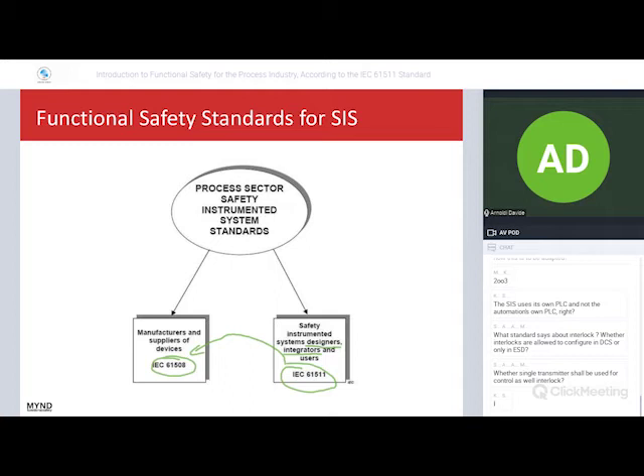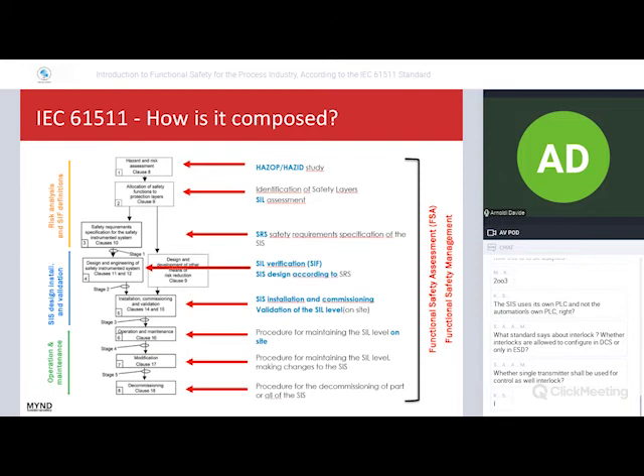This is the relationship between 61508 and 61511. How is 61511 composed? I'm showing you the life cycle of the standard. We have to follow it from the top to the bottom, from the hazard and risk assessment to the decommissioning of the safety instrumented system.